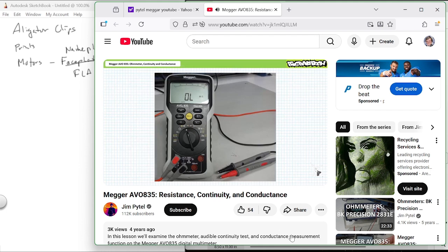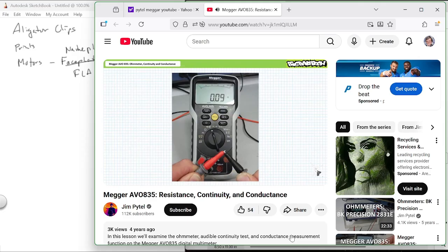In the current configuration, the DMM displays OL, which is shorthand for over limit, indicating the resistance between the two probes is too great to be measured, which implies an open circuit. This is the DMM's way of telling us there is no conductive path between the two probes. When I touch the probes together, resistance plummets, indicating the test leads present an extremely low resistance path. This is an excellent way of function testing the leads. Leads with a break would indicate an open circuit and would not be suitable for testing the resistance of other elements. Now that we're certain we've got a functional set of probes, let's test the resistance of some electrical components.